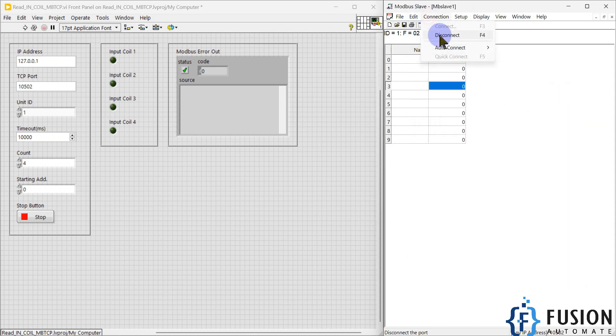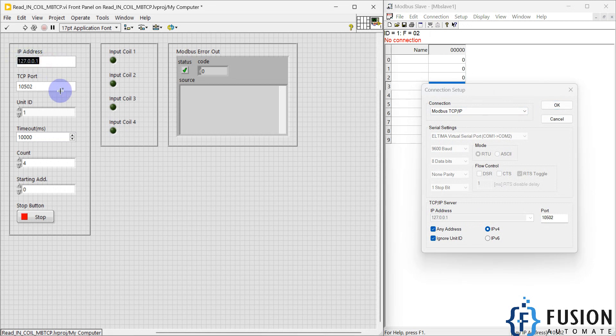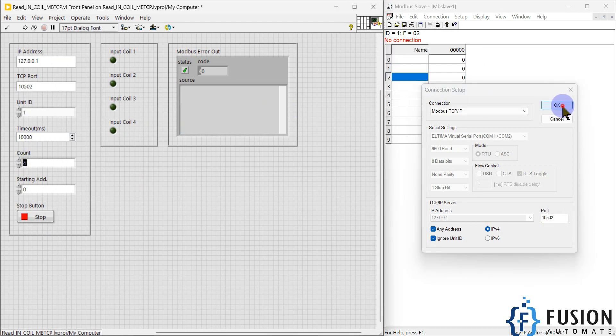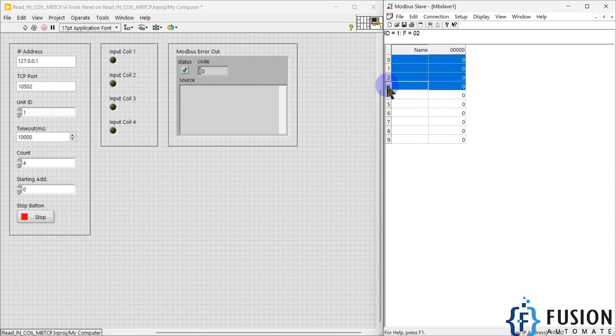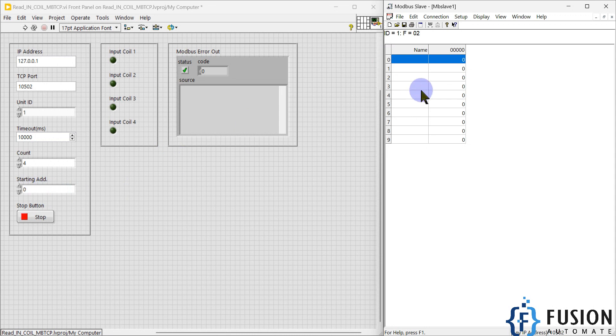The slave ID is 1. The connection type is Modbus TCP/IP, IP address is 127.0.0.1, and port number is 10502. Unit ID is 1, timeout is 10,000 milliseconds, count is 4 because I want to read four discrete coil statuses, and the starting address is 0 — meaning I want to read from the zeroth coil.